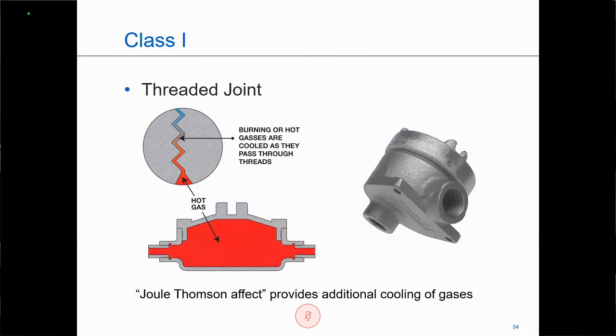Now, there's something else that takes effect, the Joule-Thomson effect. Sometimes people will affectionately call this the refrigeration effect. And what this is: anytime something passes from a high-pressure system to a low-pressure system, there's an additional cooling.